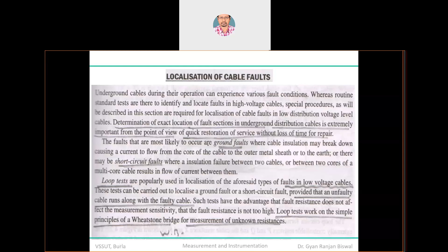In both cases, the arrangement is the same, but as far as the technical management is concerned, for the measurement of the fault at an unknown location, that is different. So I will tell you one by one. The limitation of the Murray loop test is that you have to implement it at ground level. There is no experimentation; you cannot conduct it.